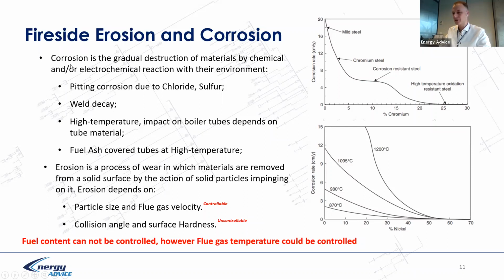Okay, corrosion effects, we have quite a lot: pitting, weld corrosion, high temperature corrosion, fuel ash covering tubes at high temperature. However, we should understand a couple of things: what we can do and what we cannot do. If the fuel contains chloride and sulfur and other alkalines, in fact we cannot change the fuel at the moment when we burn it. At the moment when the fuel is burning, the fuel cannot be changed.